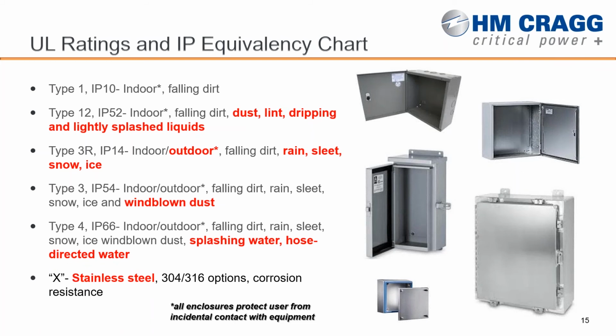Next level up would be type 12. It's also considered an indoor enclosure. It is basically filtered. The air coming in is actually filtered through it. So it protects against dust, lint. It has the ability to protect the equipment from some dripping water or some light splashed liquids. It typically has a solid front door rather than a fully vented front door, but they will also have ventilation fans on them. The ventilation fan will have a filter and a grill assembly. So in an industrial environment, where would you see these? In an industrial environment, a manufacturing space, somewhere where the air quality is not as well regulated, then we might want to look at a type 12. Again, but indoor.